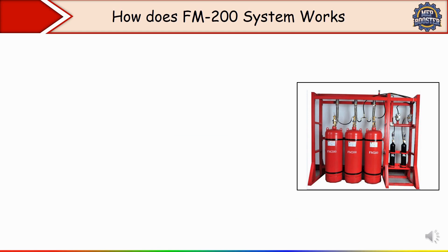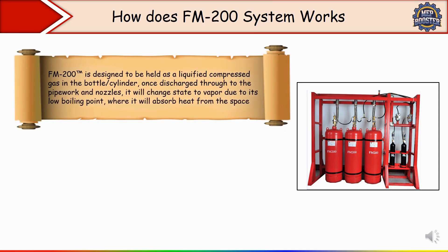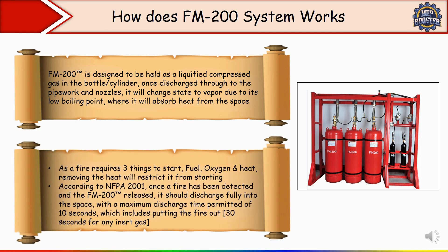Now we'll see how the FM-200 system works. FM-200 is designed to be held as a liquefied compressed gas in a cylinder. Once discharged through the pipework and nozzles, it changes state to vapor due to its low boiling point, absorbing heat from the space. Since a fire requires three things — fuel, oxygen, and heat — removing heat restricts it from continuing. According to NFPA 2001, once a fire is detected and FM-200 is released, it should discharge fully into the space within a maximum permitted time of 10 seconds, including putting the fire out.